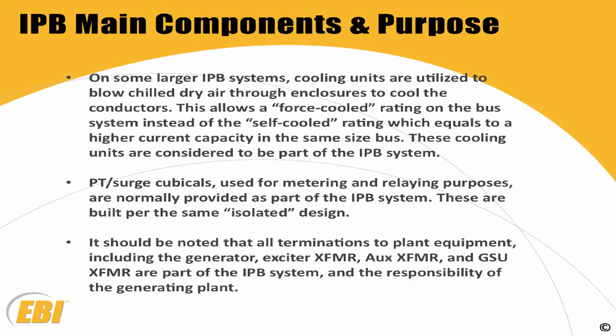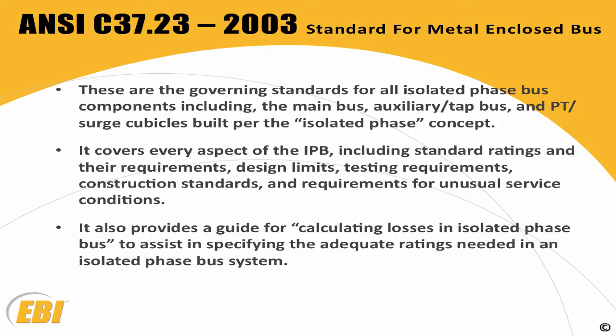One other thing that really needs to be noted is that the terminations at all the plant equipment, including your generator and all the transformers, including the GSU transformer, are part of the IPB system, and they are a responsibility of the generating plant. ANSI C37.23 is the standard that covers all your isolated phase bus, and actually it covers all your non-seg bus also. They will tell you what the ratings of the bus are, the design limits, the testing that has to be done on the bus, all the construction standards, and it also gives you requirements for unusual service. It also gives you a guide for calculating the losses inside the isolated phase bus when you specify the bus in a new system.